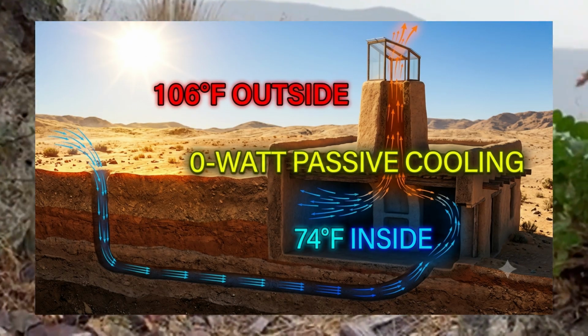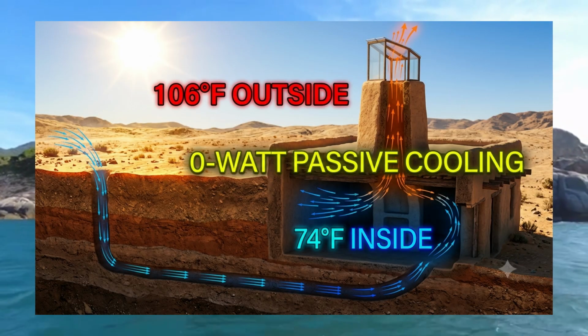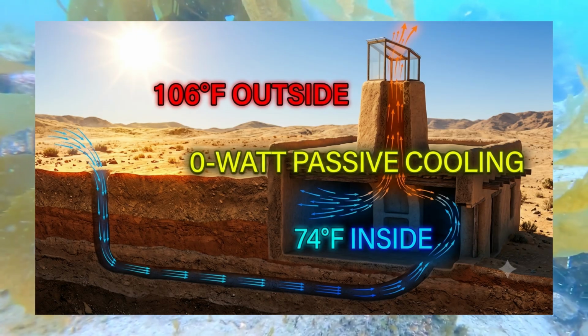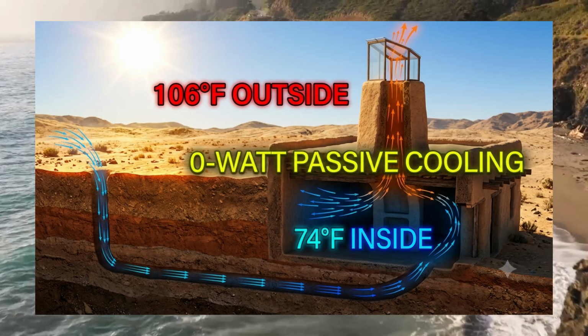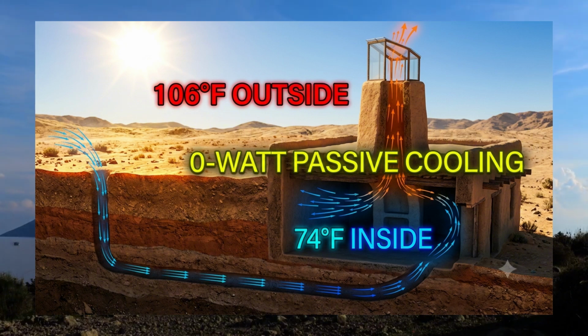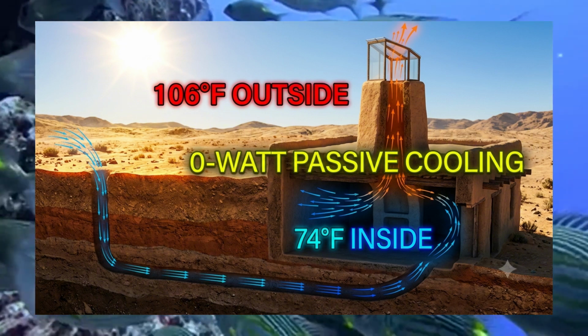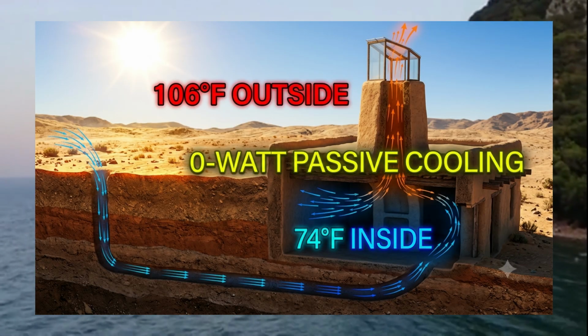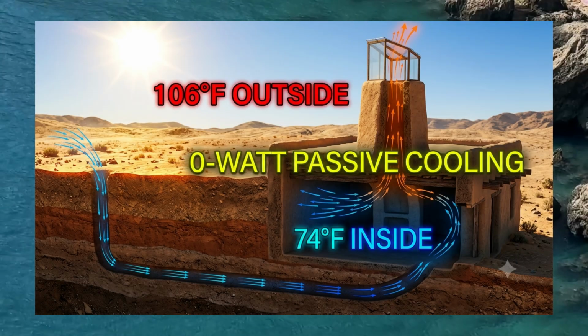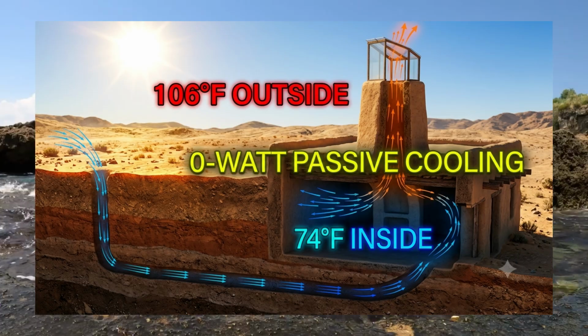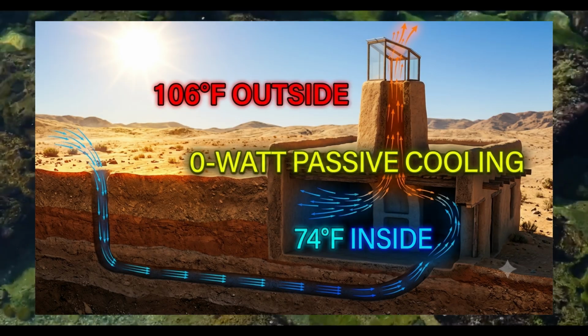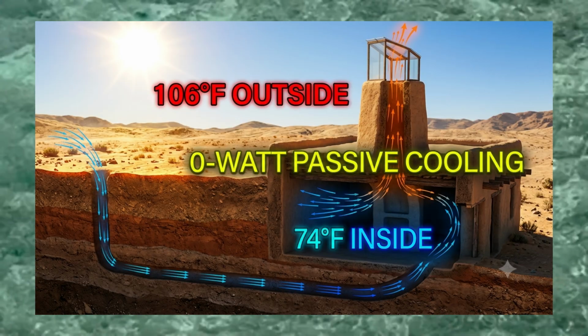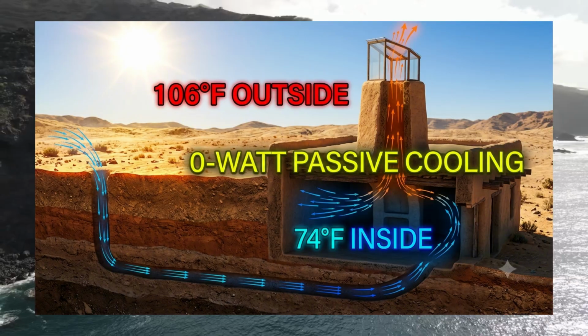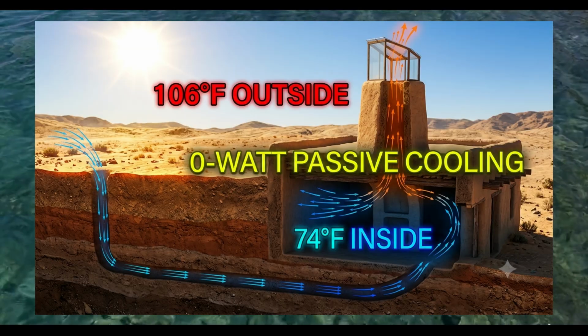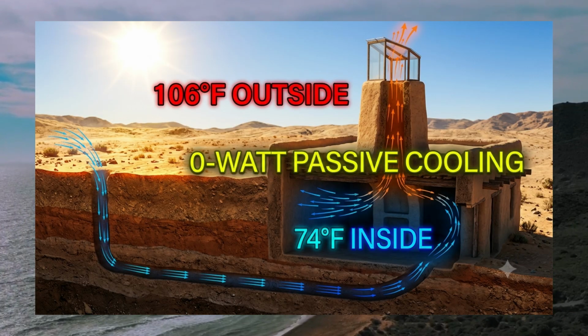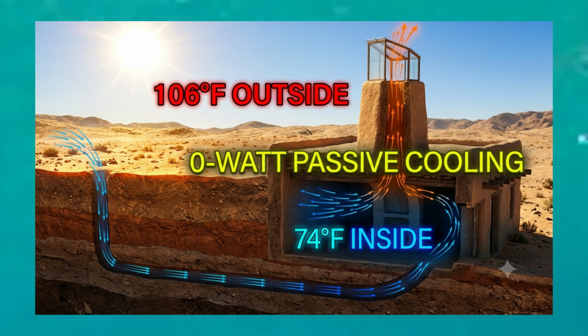This is why the integration of subterranean earth tubes is so critical. Unlike the cool tower, which relies on evaporation, the earth tubes cool the air through direct, sensible heat transfer with the cool earth. Even when the monsoonal humidity spike crippled the cool tower, the earth tubes continued to deliver cool, dry air to the home, allowing the occupant to close the cool tower dampers and switch the home's intake entirely to the subterranean loop. This hybrid functionality is what separates a scientifically engineered passive home from a simplistic, single-system design. It proves that by understanding the psychrometric chart and knowing when to shift between sensible and latent heat rejection, we can maintain comfort throughout the shifting phases of the summer season.